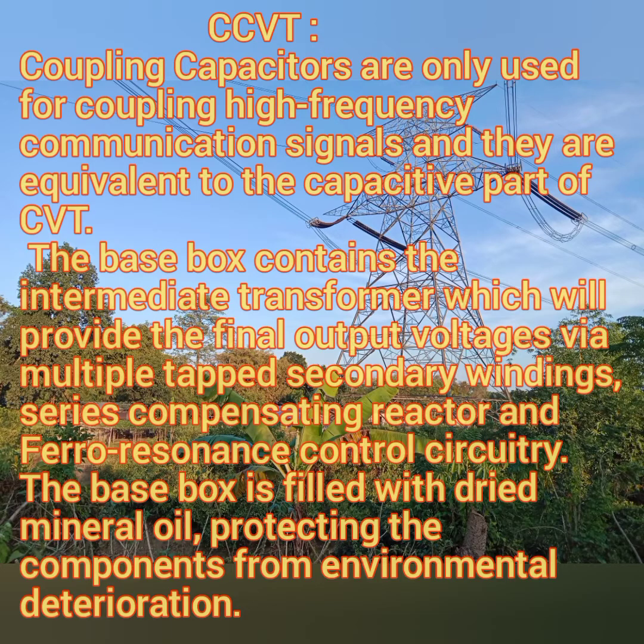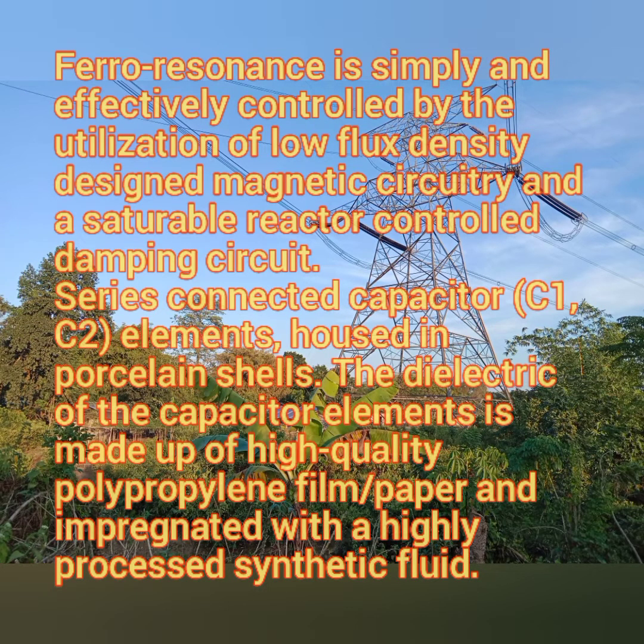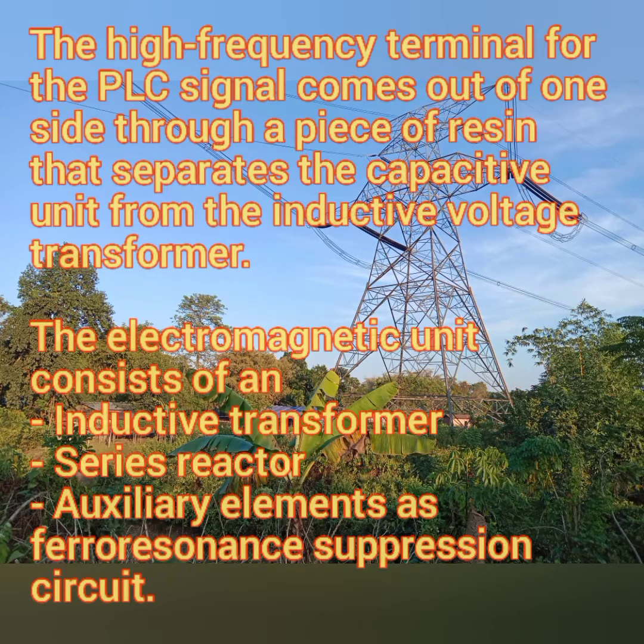Normally, ferroresonance is simply and effectively controlled by the use of a low flux density designed magnetic circuit and a saturable reactor controlled damping circuit. Series connected C1 and C2 capacitors are housed in porcelain shells. The dielectric of the capacitor element is made up of high quality polypropylene film or paper and impregnated in a highly processed synthetic fluid.